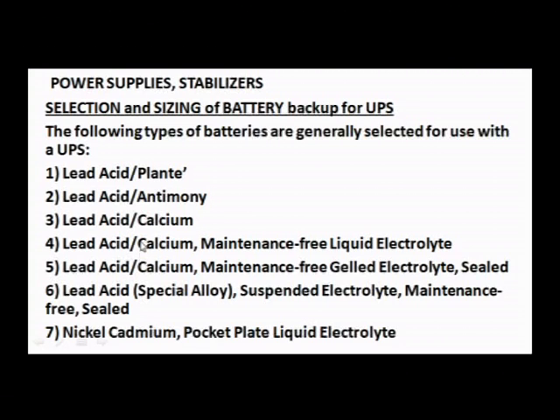But a few types are maintenance-free: lead calcium maintenance-free liquid electrolyte, and maintenance-free gelled electrolyte, which is sealed - you just connect it and leave it, it works. Then there is lead acid special alloy suspended electrolyte, maintenance-free and sealed. The electrolytes are of different types: liquid, gel, suspended. Finally, nickel cadmium, which is pocket plate liquid electrolyte. These are the various types of batteries you can connect for your UPS.